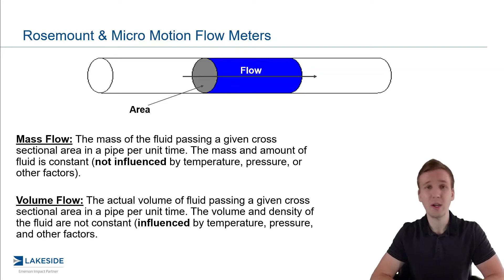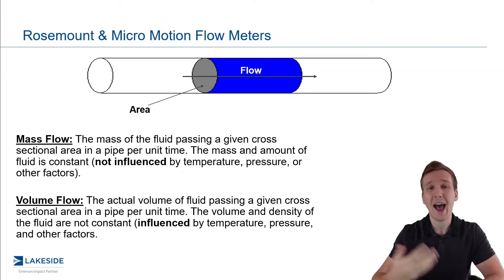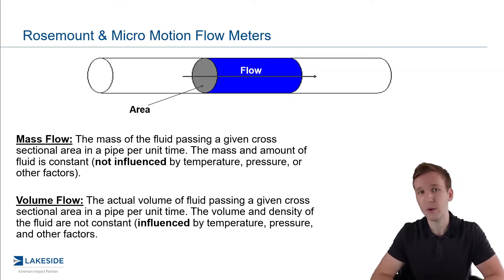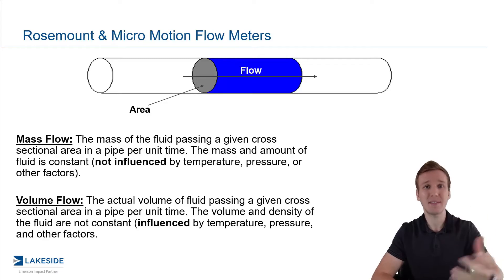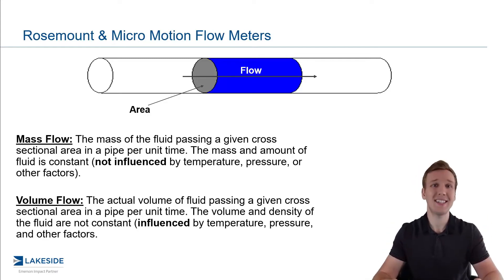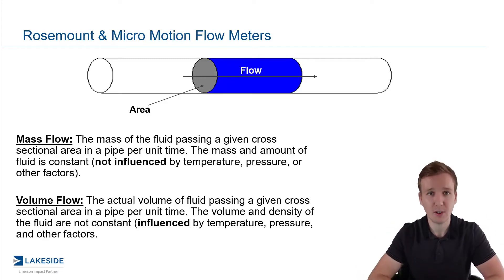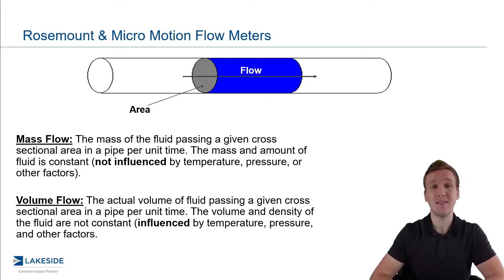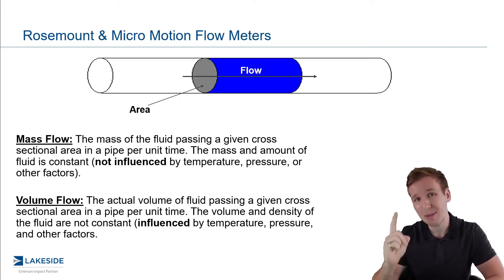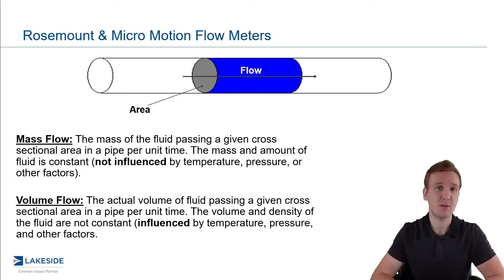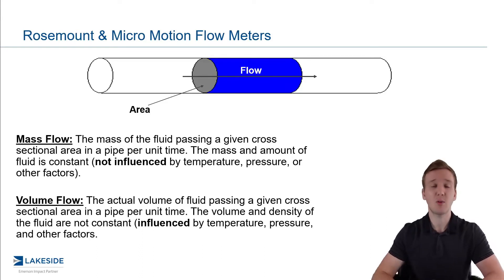The big difference between these two is how we actually measure the amount of fluid. We can do this in terms of the mass of the fluid, which is consistent and independent of pressures and temperatures. Or we can measure it in terms of volume, and the volume is going to be dependent on the pressure and temperature. That's a big, big difference to understand between these two measurements.